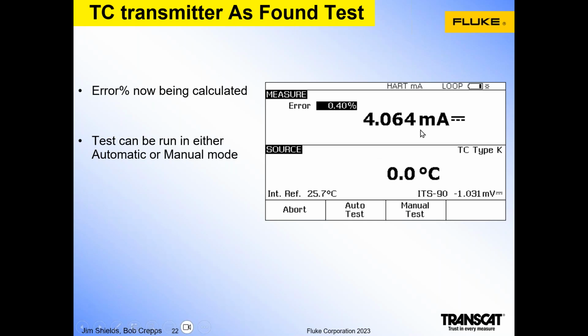Here's the temperature that the calibrator is applying, 0 degrees C for a type K thermocouple, and it's measuring 4 milliamps. And 4.064 milliamps is greater than the allowable test tolerance, apparently, because this error is showing in reverse video. Here, the error percent shows the deviation of the measured milliamp signal when compared to nominal. And at this point, the test can be run automatically or manually, and each calibration point accepted by the calibration technician.